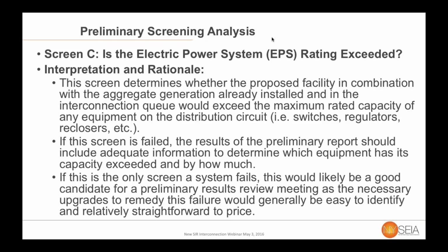And so if you exceed the rating of any of the equipment, switches, reclosers, what you will see is the list of all of the systems, what their rated capacity is, what the aggregate DG is, plus your system, and then you can see by how much, if at all, you exceed any of the ratings for that equipment. And so this is one of those screens where the preliminary results meeting that Melissa mentioned can be a very useful part of this new process.